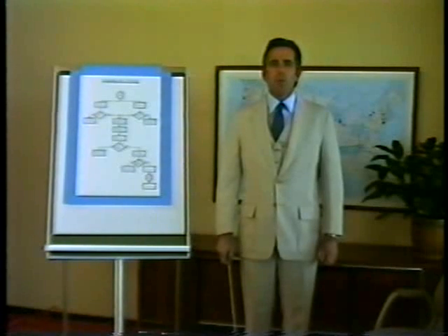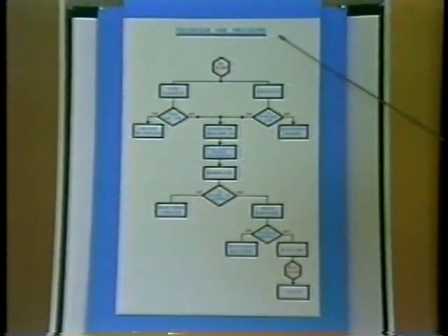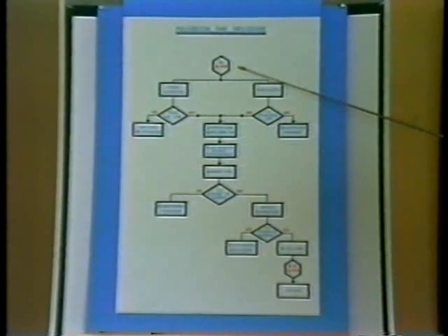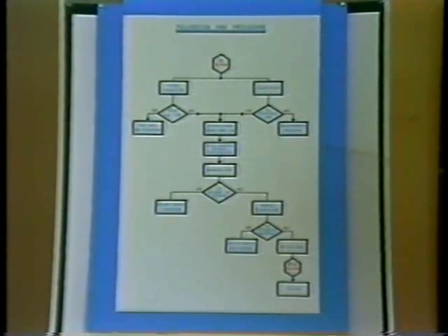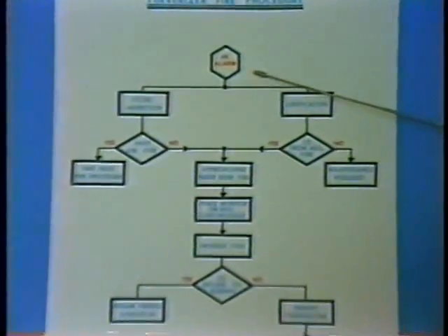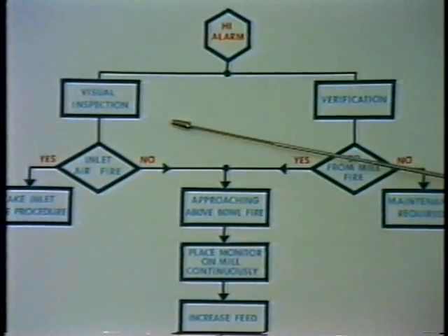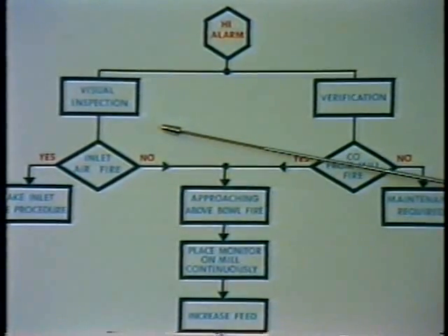Every facility has its own methods for pulverizing coal and dealing with coal fires. Here at KVB, we recognize this and follow up at your request to help your staff design a plan to fit your needs. This pulverizer fire procedure was developed for one of our clients and is very site-specific. The plan is based on a two-tiered level of concern, one at low carbon monoxide levels and one at relatively higher carbon monoxide levels. When the operators are alerted to a high alarm, they perform a visual inspection of the pulverizer to see if there is an inlet air fire taking place.